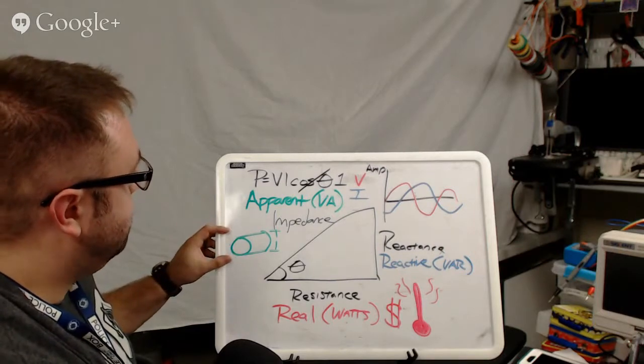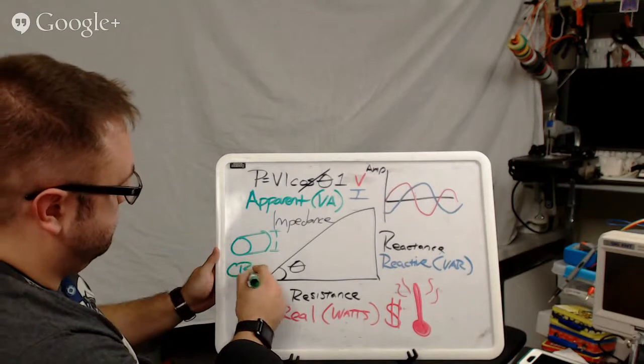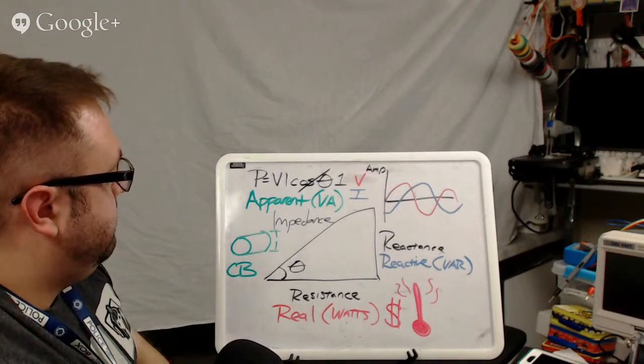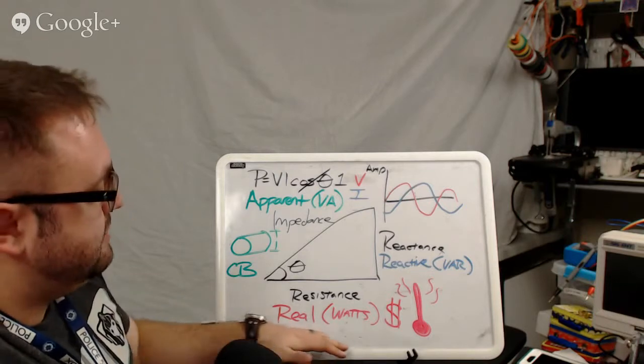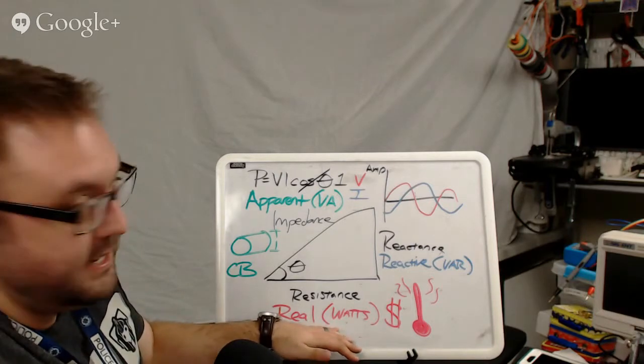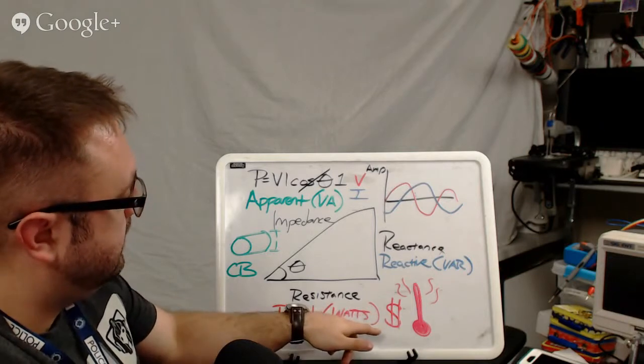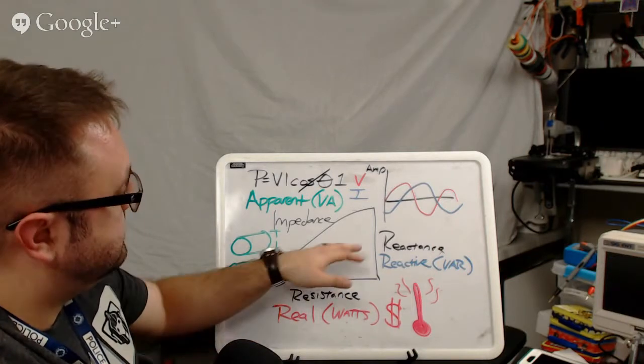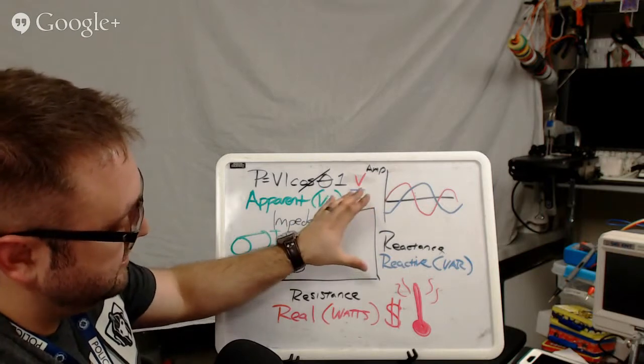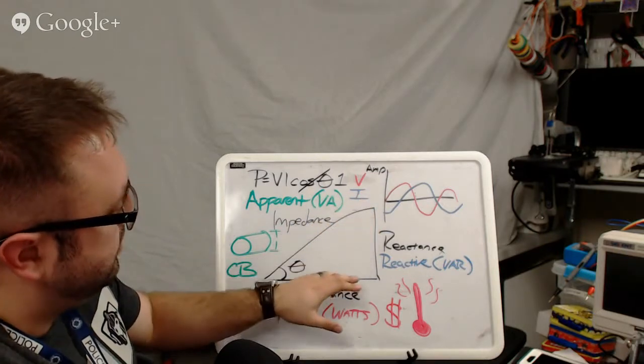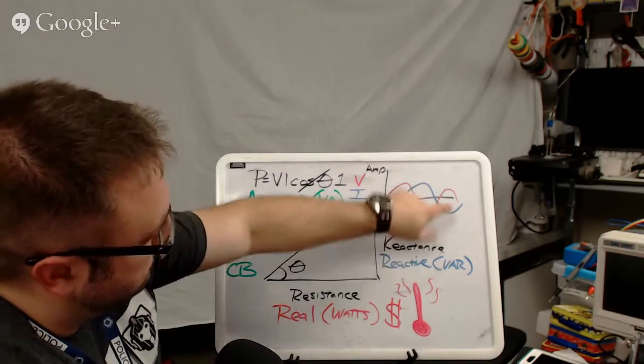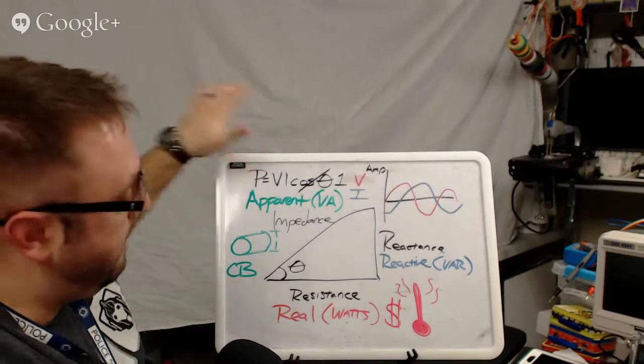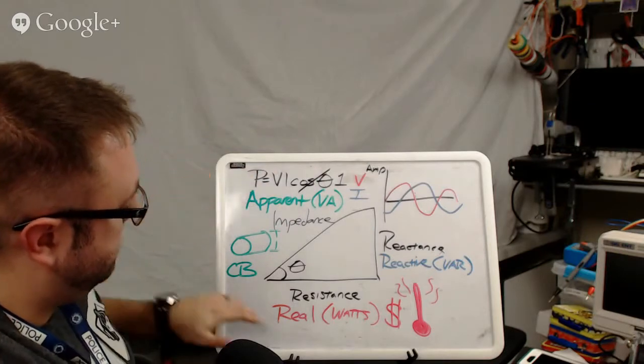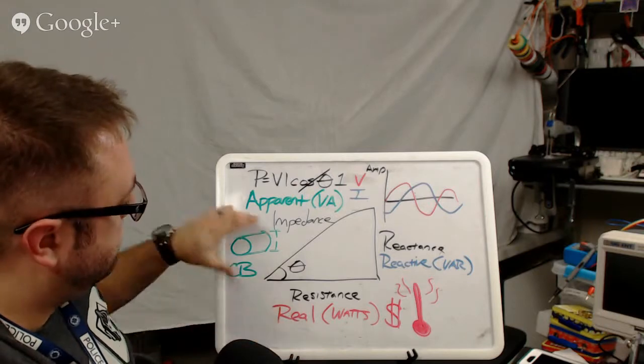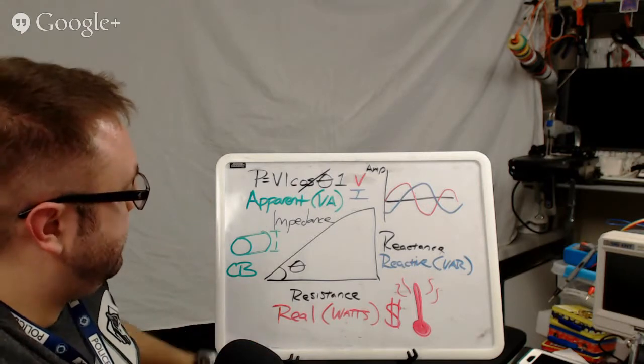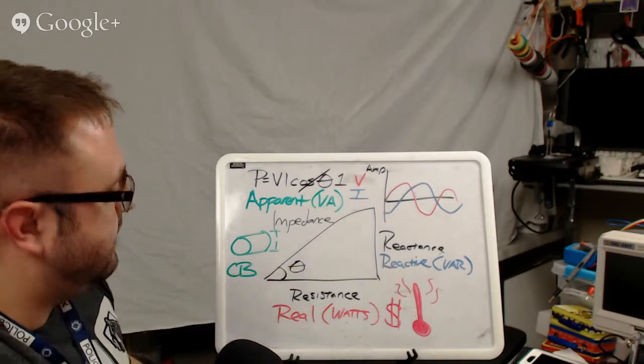It's also used for sizing our circuit breakers. Because yes, I'm pulling this power in off the grid and it's getting dissipated as heat, but if I'm dealing with a lot of motors, I'm producing and consuming reactive power. So there are times as I go through the cycle where I'm dumping more power into the circuit than I'm consuming or burning as heat. So my wires have to be sized to handle both the real power and the reactive power going through my system.